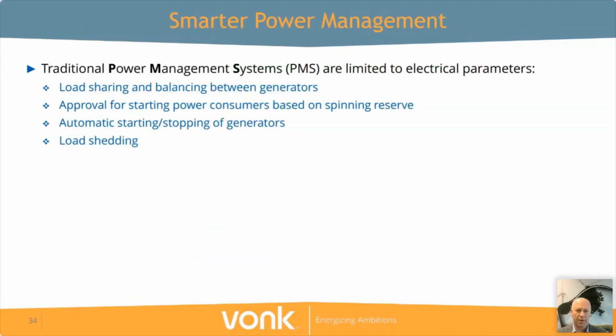Last but not least, smarter power management. Power management has always been done, but in most cases this is limited to electrical parameters: load sharing and balancing between generators, approval for starting up certain consumers at your plant, acting based on the spinning reserve available in your generators, automatic starting and stopping of generators, and load shedding.